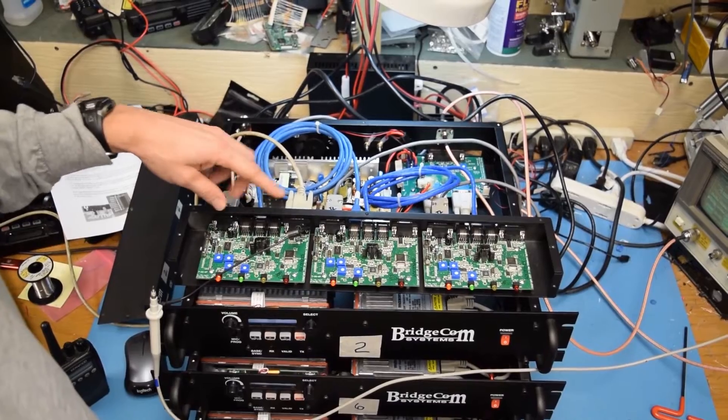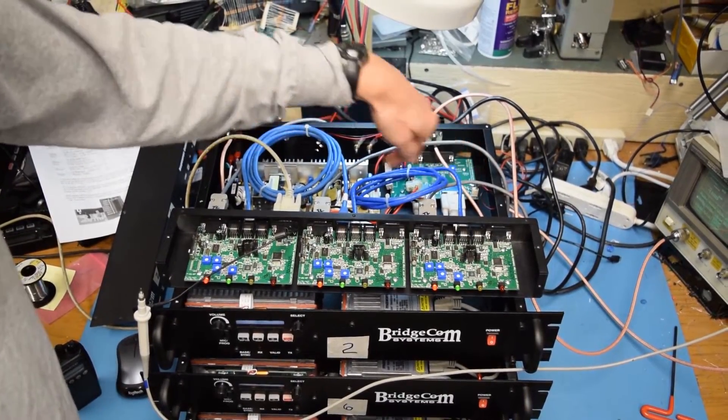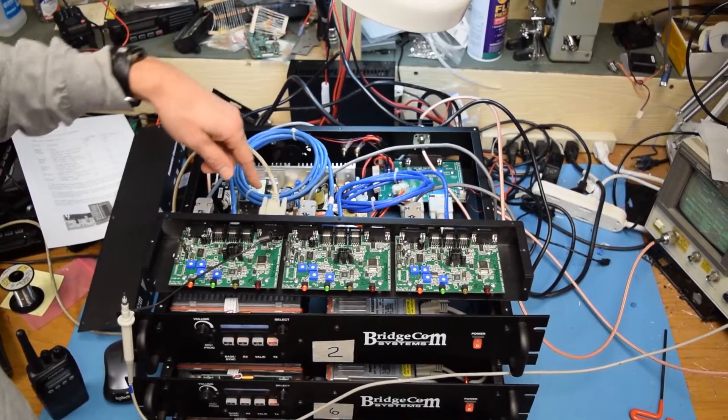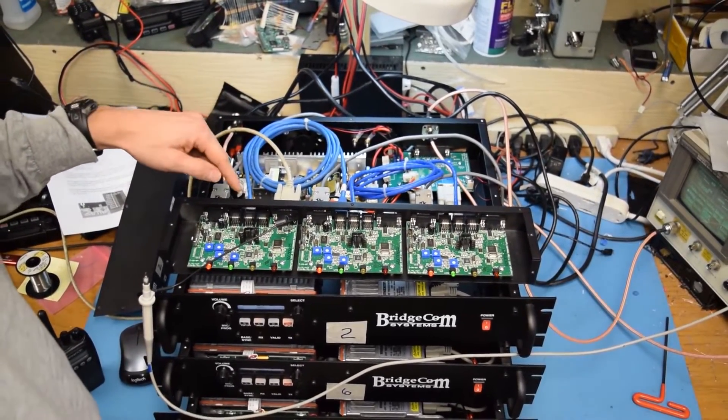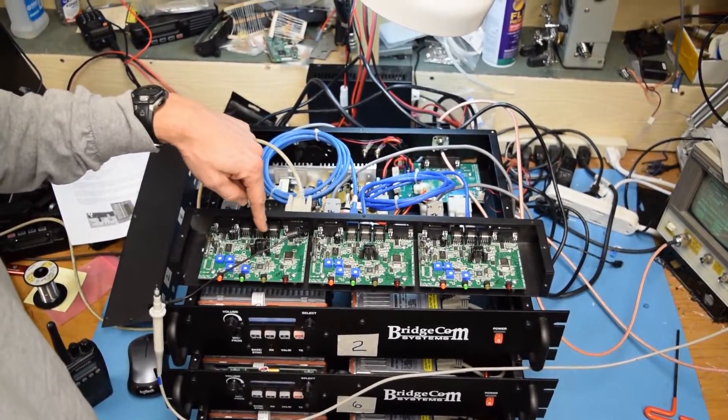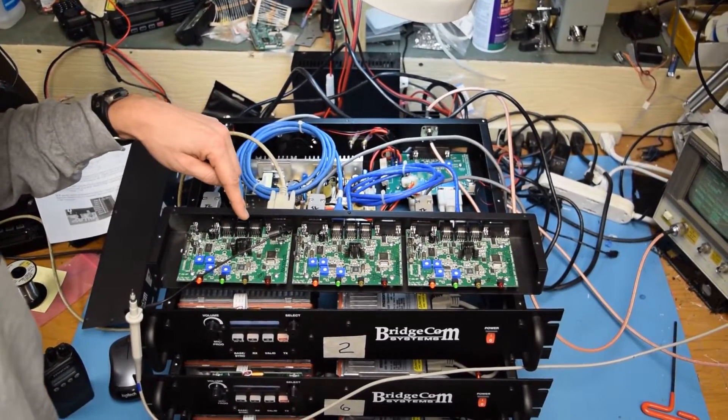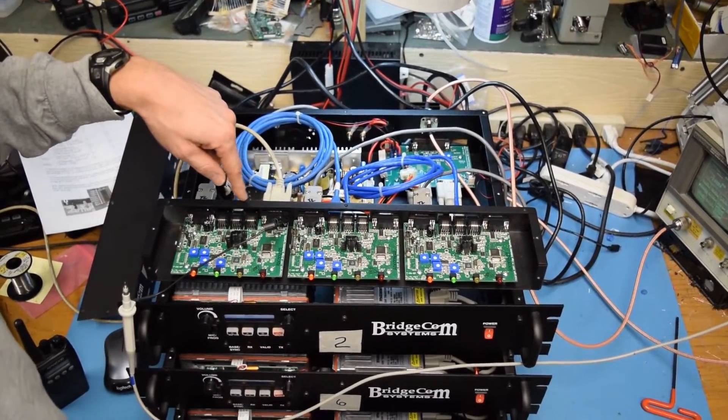Now, the bus that transports this information is an RS-485 bus, and it requires terminators. The terminating resistors are located behind the voltage regulator. They're labeled J16 through J20.